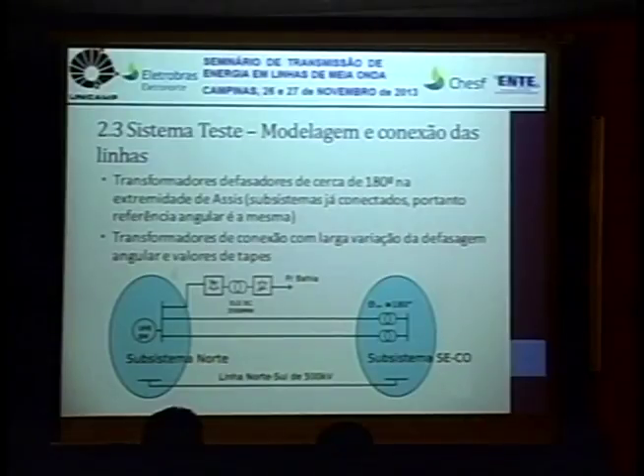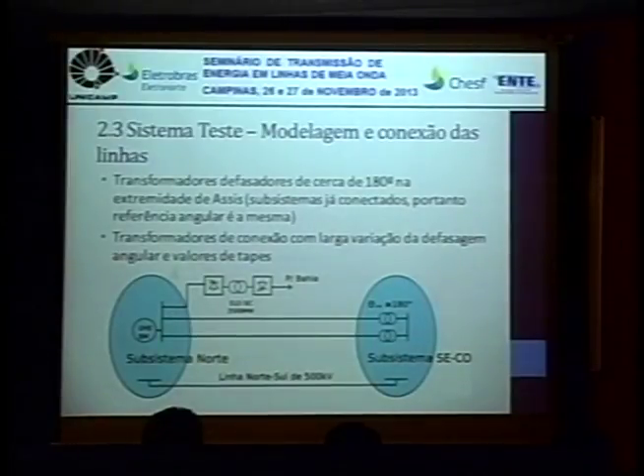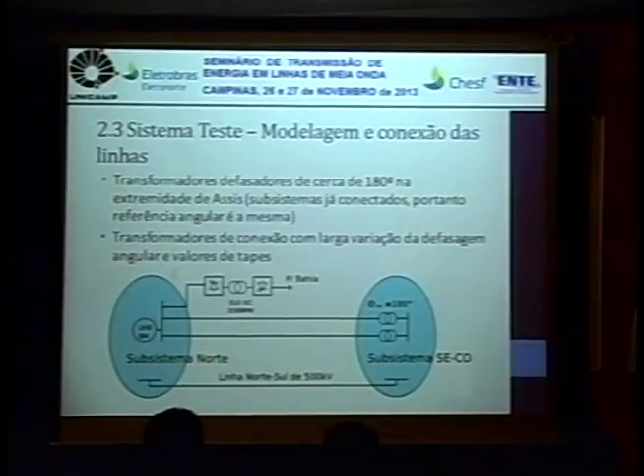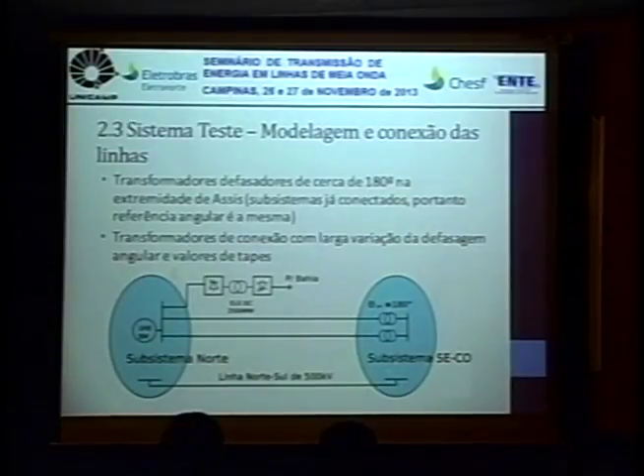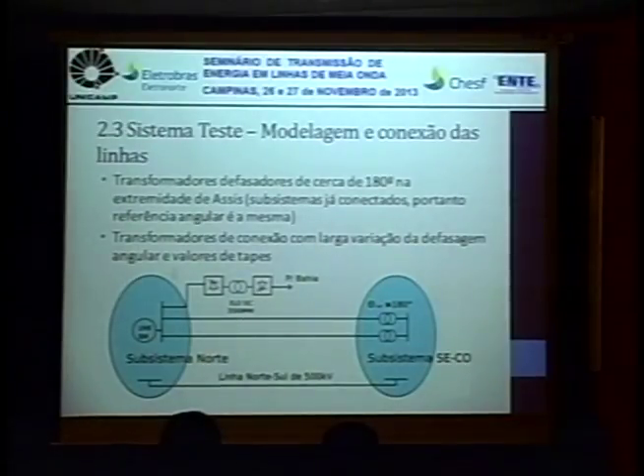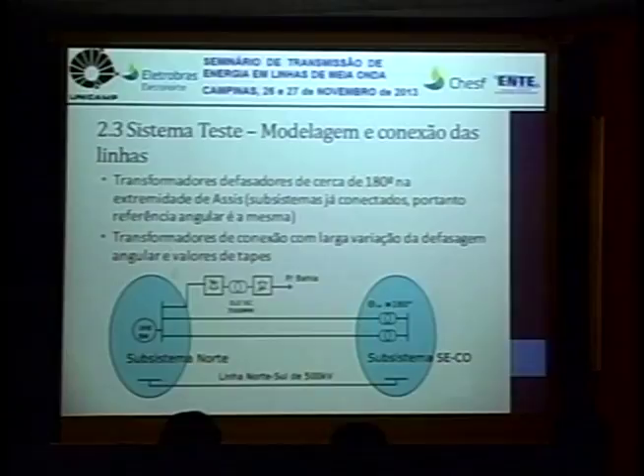It was also necessary to put the 180-degree transformers at the Assis terminal to compensate the problems with the half-wavelength line. In the base case, there was already a 180-degree transformer, and the AC link for Bahia, you can forget this thing here in the middle, but this was also modeled in the base case from EPE. Here we must remember that we're going to have parallel pathways with an interconnection between the systems, the north-south interconnection. This is something that complicates the study, because this network is going to work together with this other one.